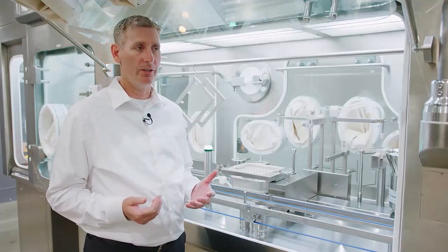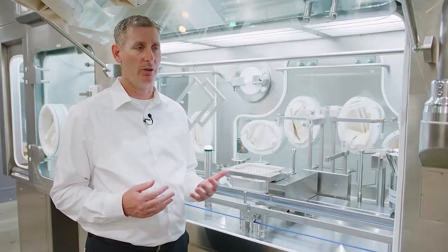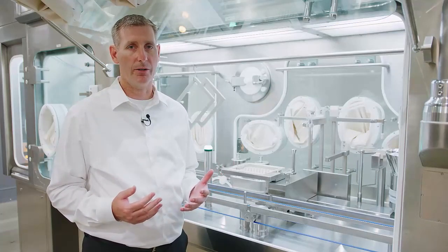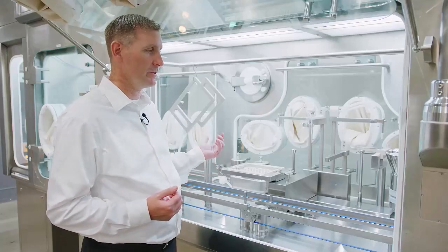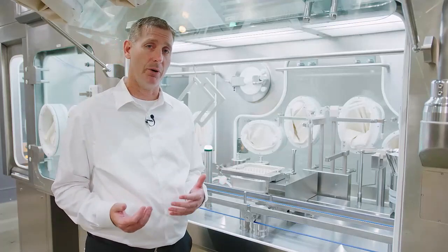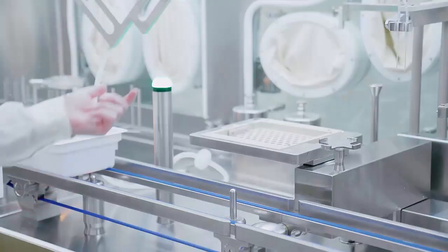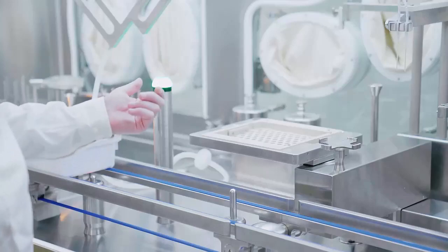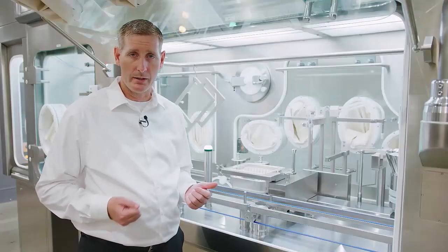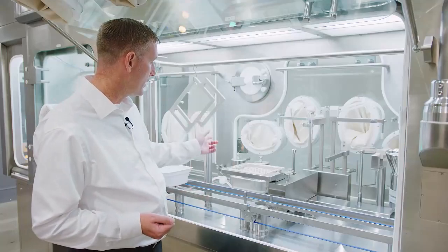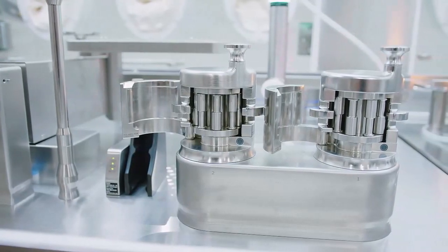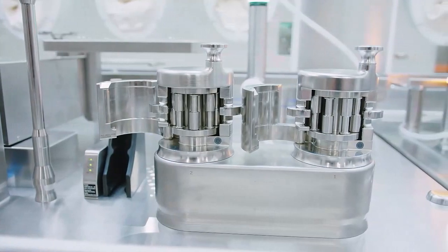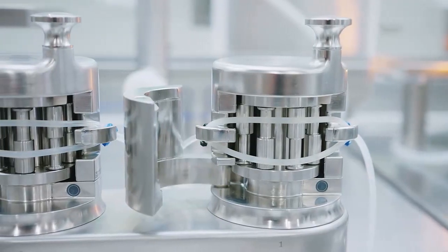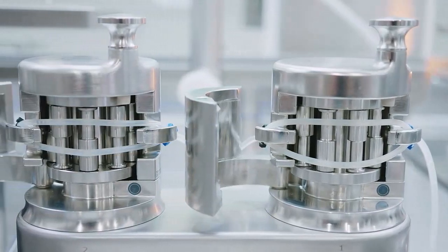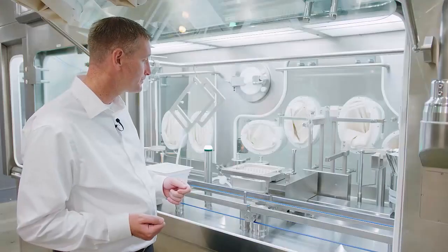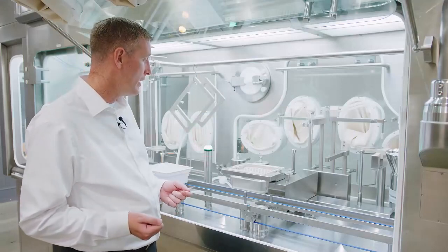As I mentioned earlier, this system is designed to fill vials, syringes, and cartridges with only the simplest of change parts. And all those change parts are designed to be interchanged depending upon the container and the process without tools. In addition to the general processing stations needed for dosing the drug product and sealing the container, we have the peristaltic pumps in the back of the equipment. Those are positioned uniquely for each glove port to easily thread the drug product single-use fluid path prior to operation. We have an IPC load cell, which we'll show momentarily.